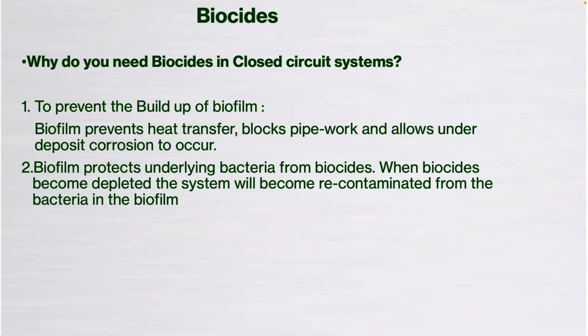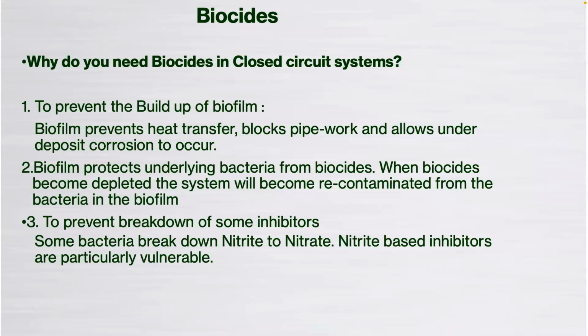So if you are using a biocide on an existing system, you need to think about pulling that biofilm out that you saw on the photograph earlier. So you need some form of biodispersant. So it's ensuring that any water treatment specialist or contractor specialist, within their methodology statement, and say, for example, you've got an old school with new plant, but you want to clean up the old system, it's important that you tackle the bacteria, you tackle the biocide with something to strip the biofilm, and then something to kill it.